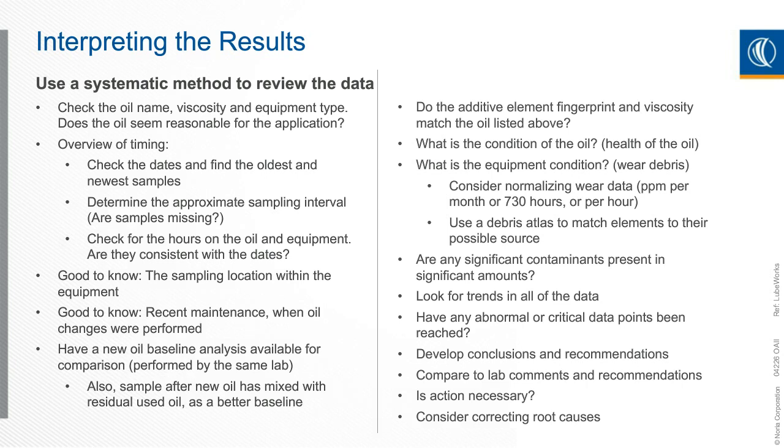So maybe it means having better breathers on your machine or having better filtration procedures to make sure your machine can get that contaminant out of there once it's introduced. Or making sure you can avoid the moisture from getting in from other sources. Whatever it may be, you need to have a better understanding of how to avoid that problem from happening again in the future.